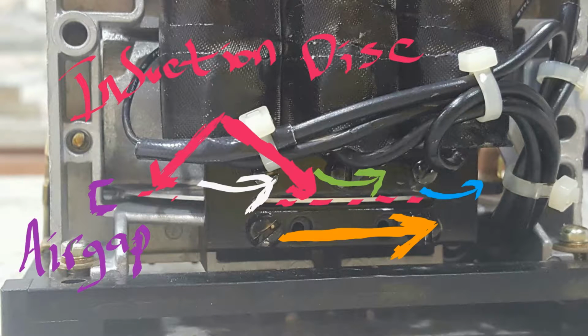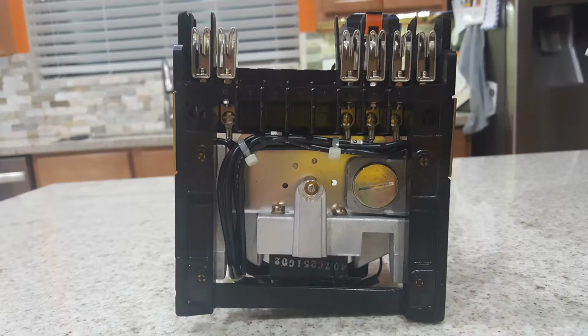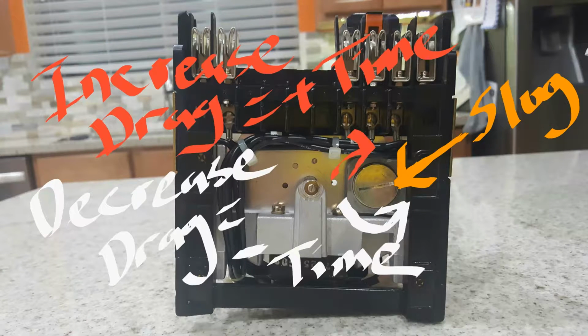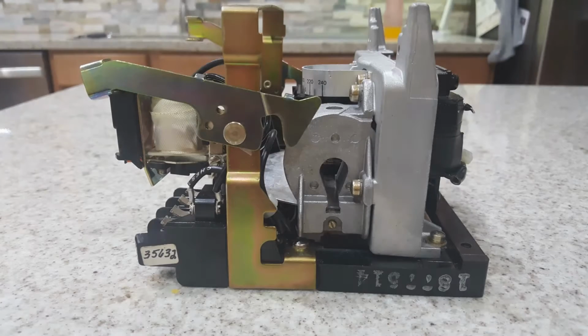Here's the simple part. Here's the air gap, the induction disc, and the EMF that makes the disc go round. From the bottom of the relay, you can see the adjustable slug that's going to affect our magnetic field, which will increase or decrease the drag on the induction disc. The adjustment, if we turn it to the right, will increase time, to the left will decrease time, for our low voltage timing test.